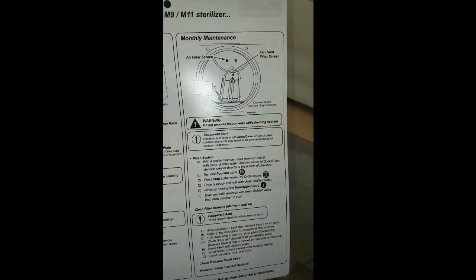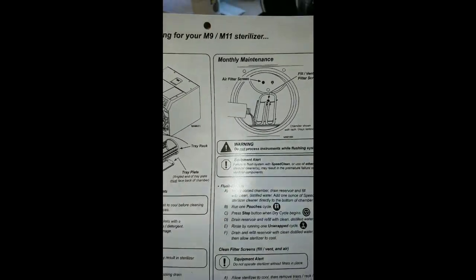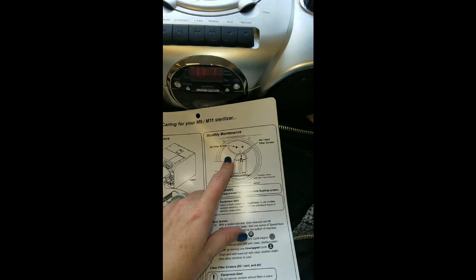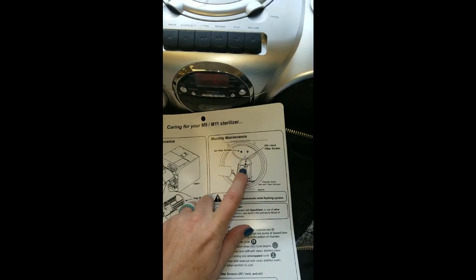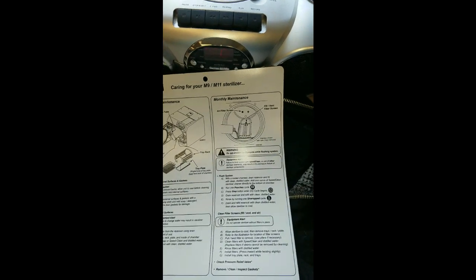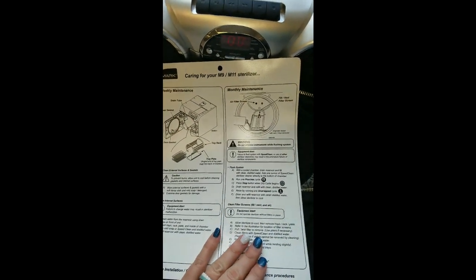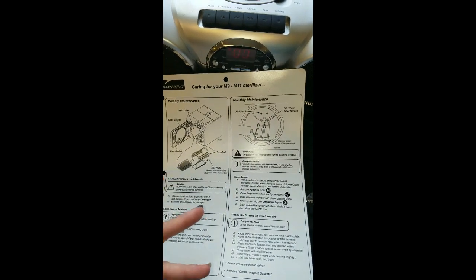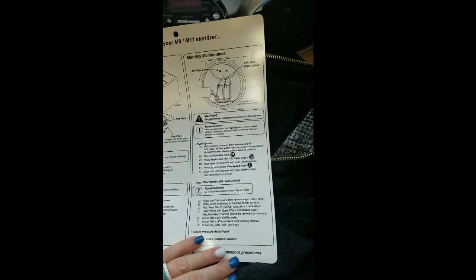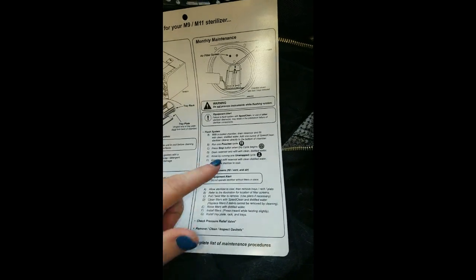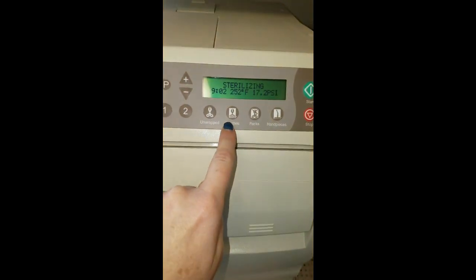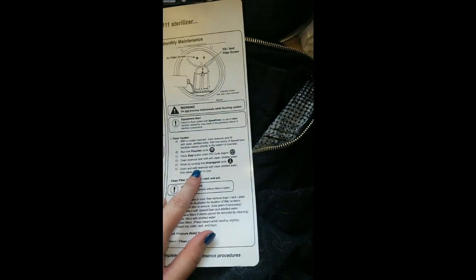For monthly maintenance, you'll go into a little more detail. What you're going to do is you have this area here where it has the air filter screen, and then the vent. And you're just going to wait for the autoclave, of course, to not have been used because you don't want it to be hot when working with it. But you'll drain it, and then you'll fill it with water, and then you'll put the SpeedClean in there, which is this stuff right here. And you'll run a pouch on the pouch cycle, which is this one right here. And then you're going to stop it when it says that it's drying. You'll stop it, and then you'll drain the reservoir and then fill it with clean distilled water.